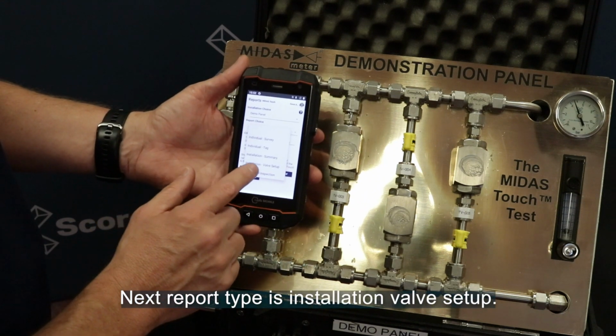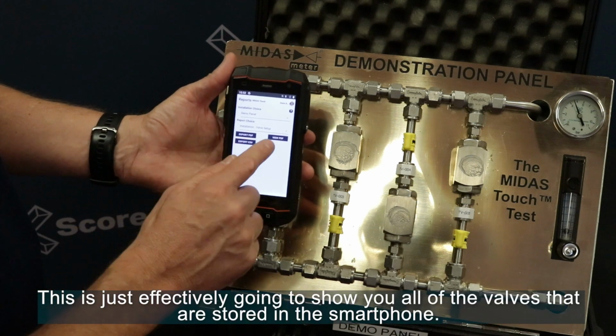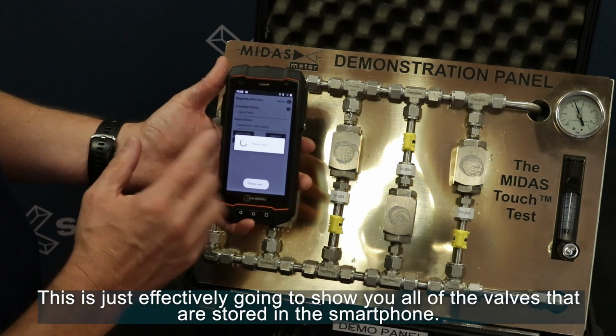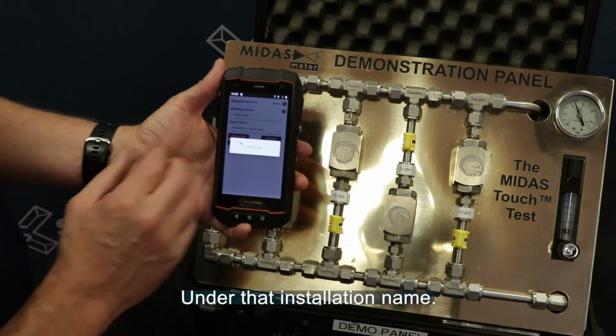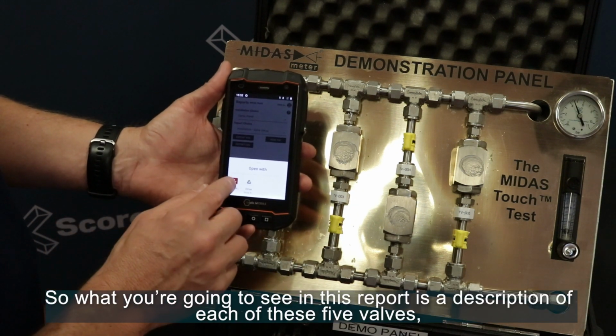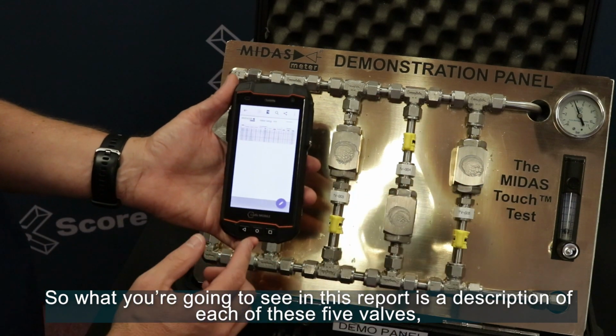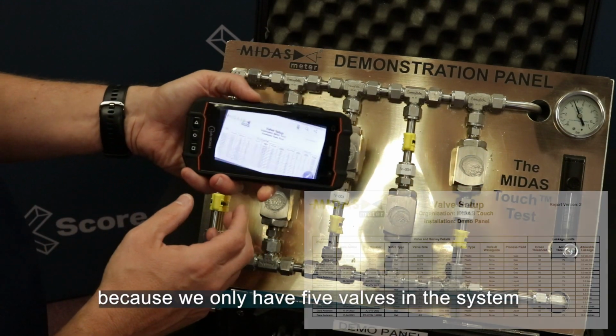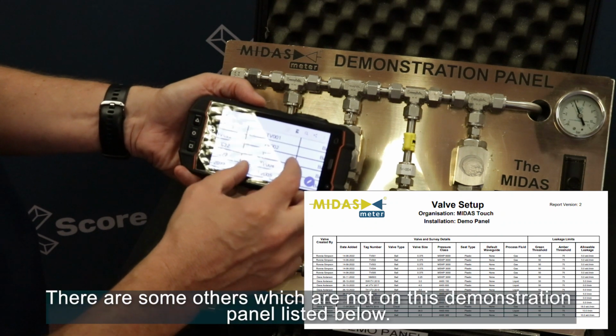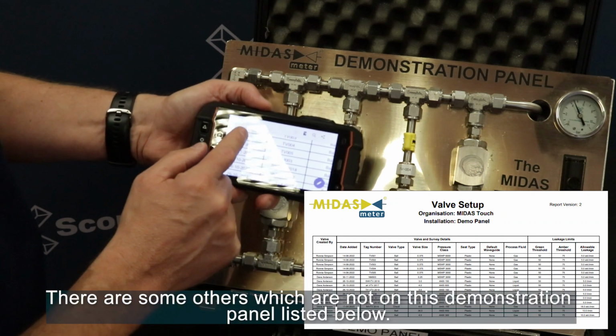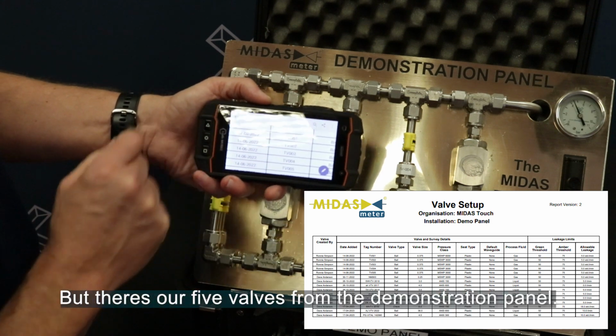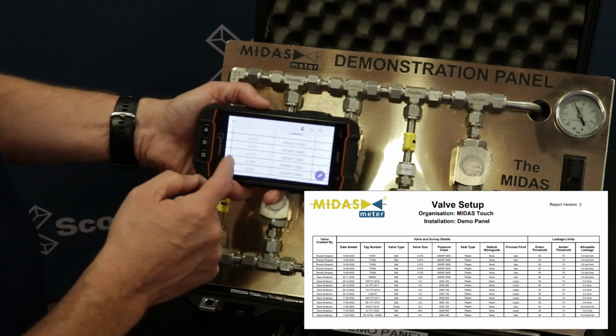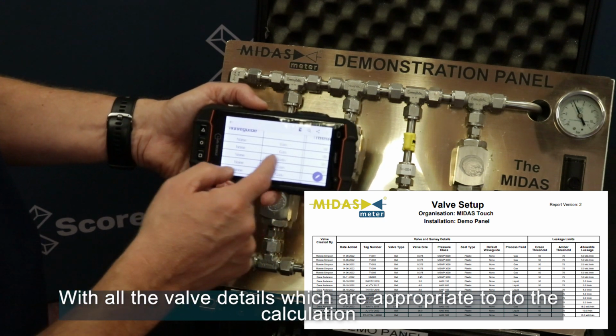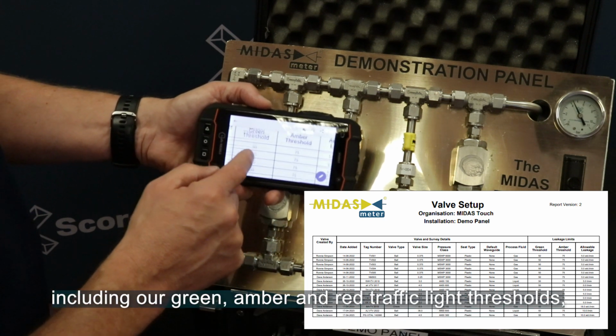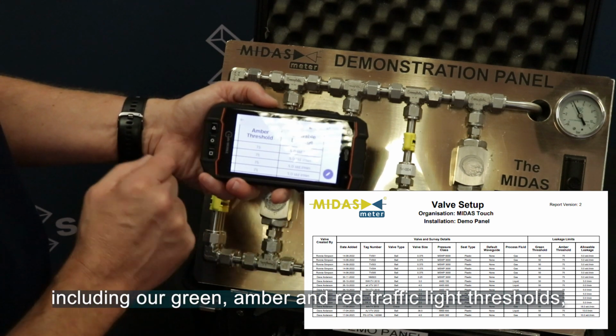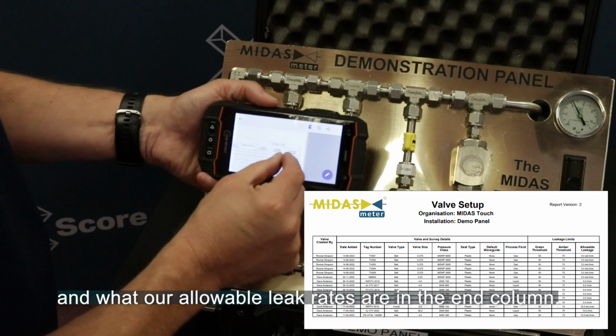Next report type is installation valve setup. This is effectively just going to show you all of the valves that are stored in the smartphone under that installation name. So what you're going to see in this report is a description of each of these 5 valves, because we only have 5 valves in the system. There are some others which are not on this demonstration panel listed below, but there's our 5 valves from the demonstration panel with all the valve details that are appropriate to do the calculation, including our green and amber and red traffic light thresholds and what our allowable leak rates are in the end column.